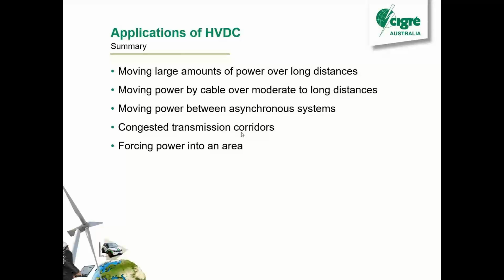And the other thing is with the HVDC, you can choose your power. The power on an AC line is determined by the physics, the angle difference and the voltage magnitude difference between the two points, and that will just determine your power flow. Whereas with the HVDC, you can choose exactly how much power you want to send, as long as the sending end and the receiving end networks can supply and receive it, it'll be able to do it. So you can manipulate the power flows, and sometimes you can use HVDC to offload AC lines or improve things, so it can be used for that.